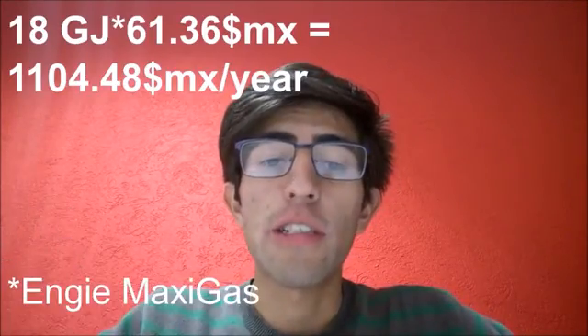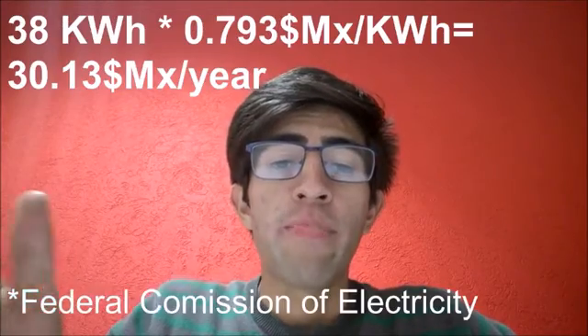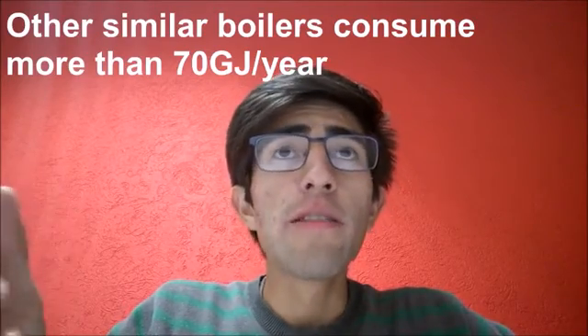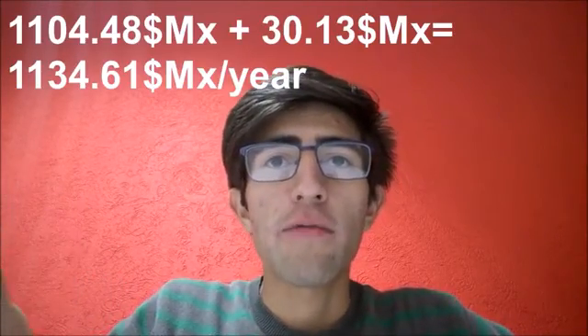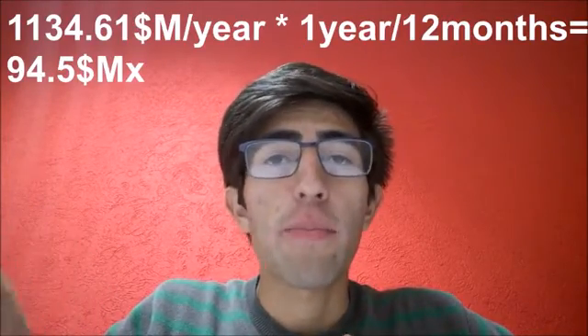And finally, we use the second law of thermodynamics, which gives us the direction and quality of the energy in the boiler. Some of the properties of the boiler that we chose are: it can reach 35 to 40 Celsius degrees, it has 92% efficiency, the annual fuel consumption is 18 gigajoules, and the annual electricity consumption is 38 kilowatt-hours. According to Engie MaxiGas and the Federal Commission of Electricity, it costs 1,134 pesos per year. It's less than 100 pesos per month.